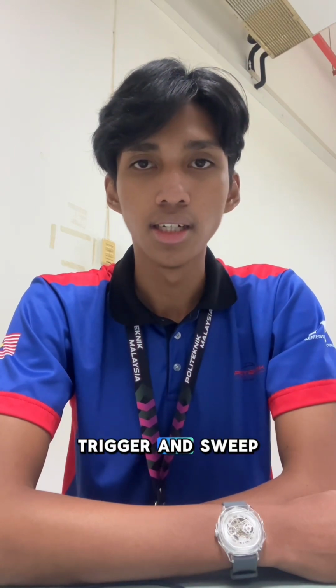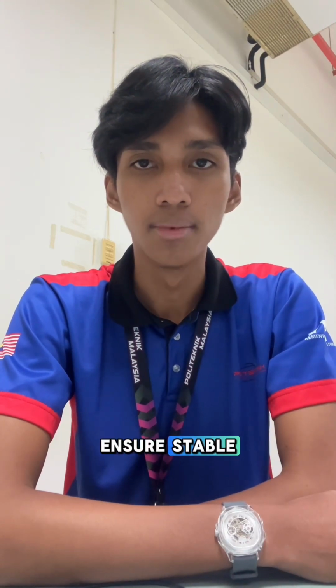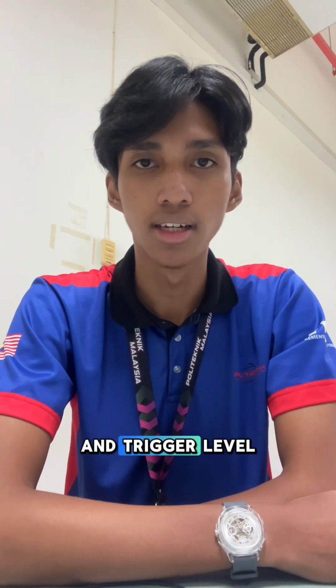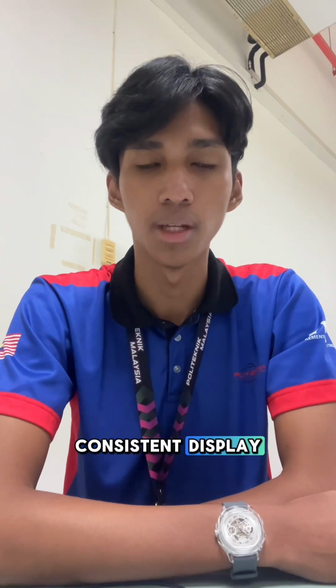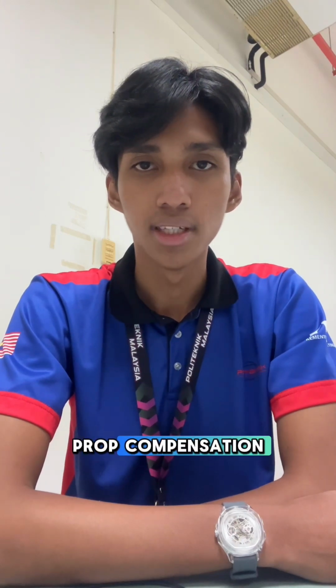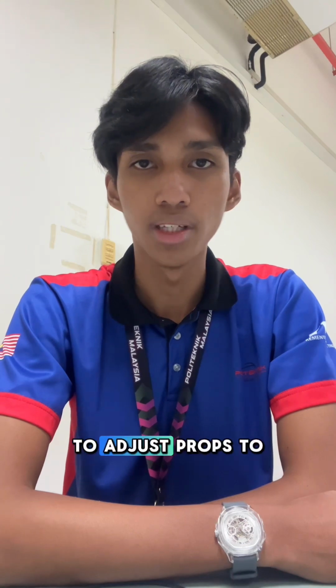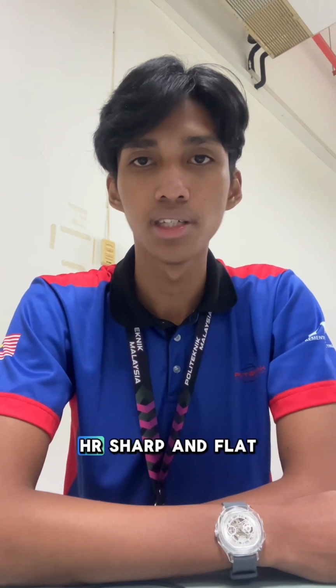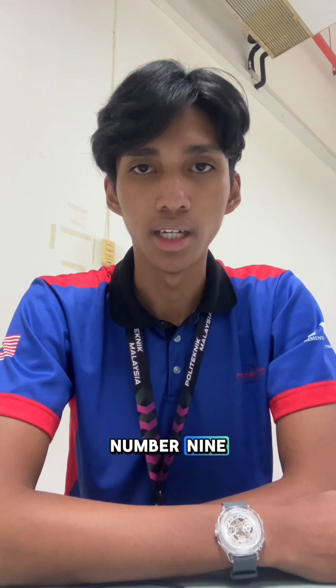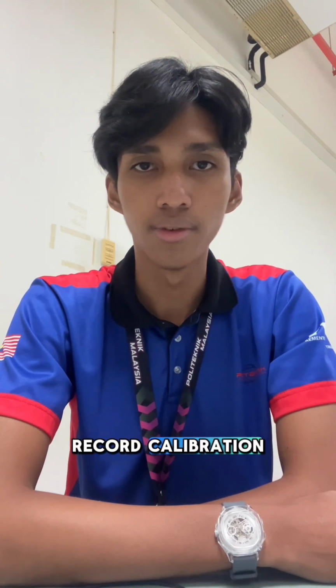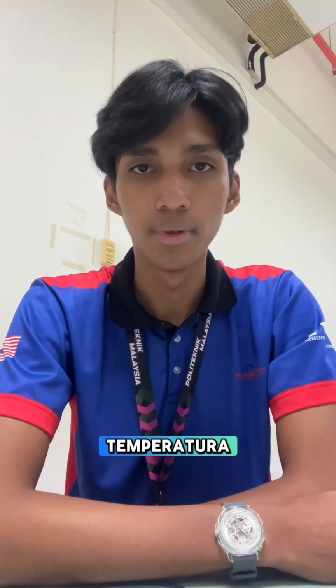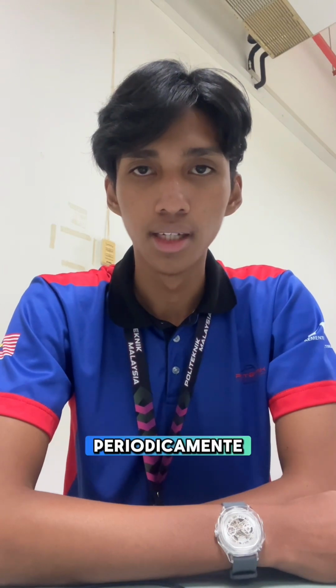Number 7, trigger and sweep calibration. Ensure stable triggering of waveforms. Adjust sweep linearity and trigger level to maintain a consistent display. Number 8, probe compensation. Use the square wave to adjust probes until waveform edges are sharp and flat. Number 9, document results. Record calibration values and deviation. Record environmental conditions, temperature and humidity, for traceability. Number 10, repeat periodically. Perform calibration at regular intervals.